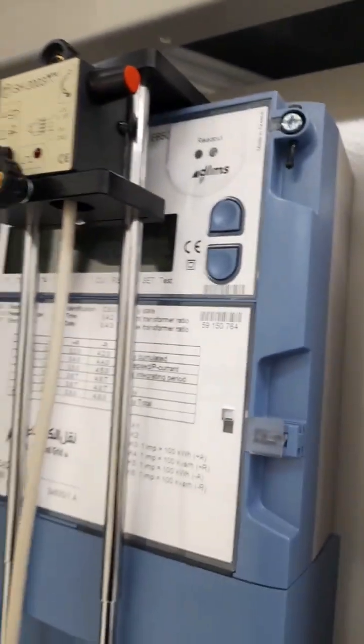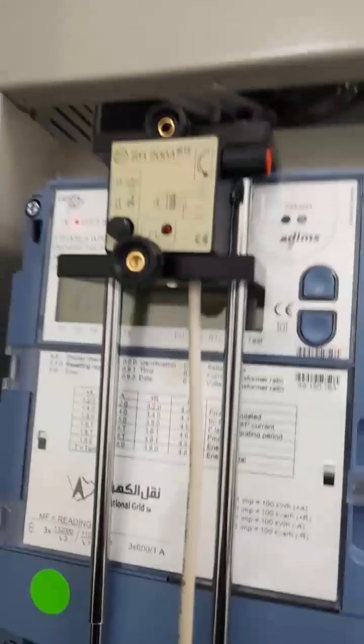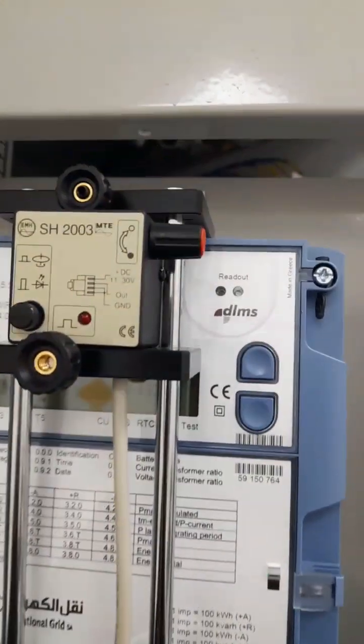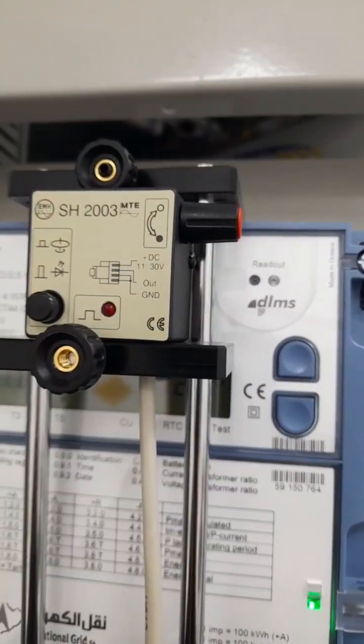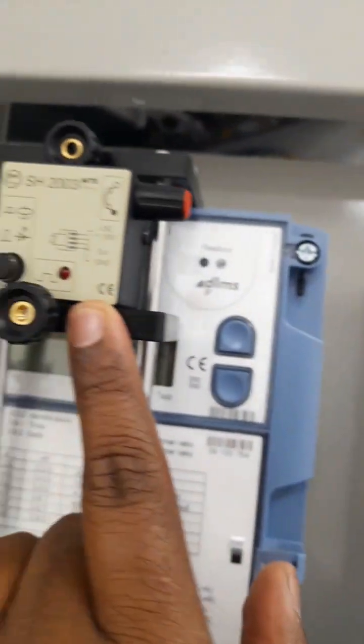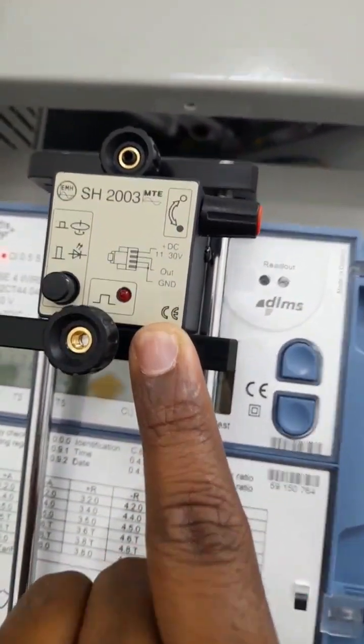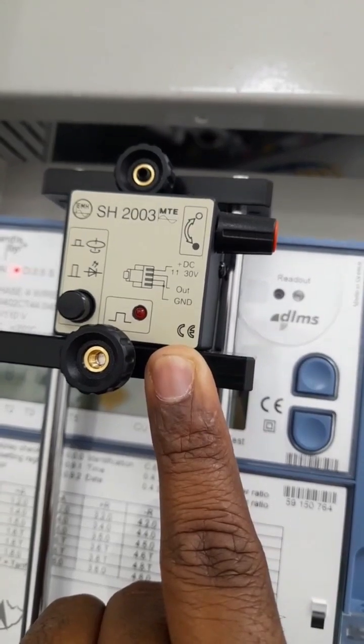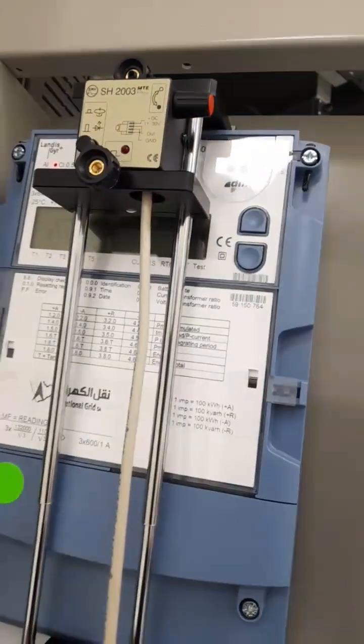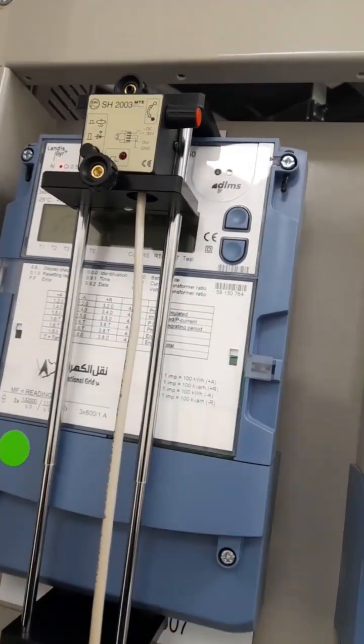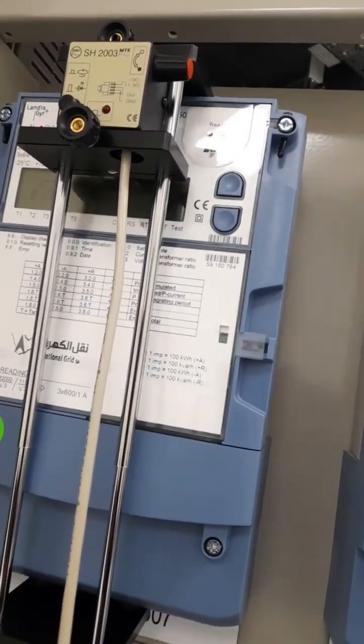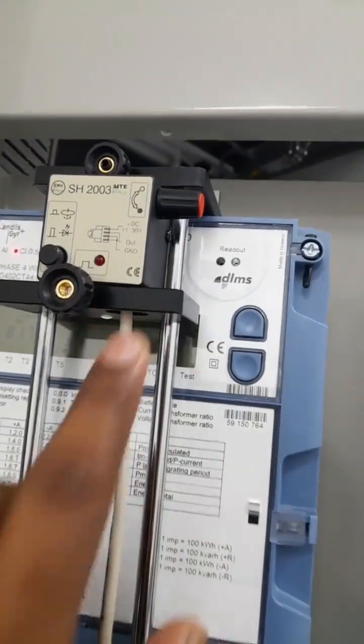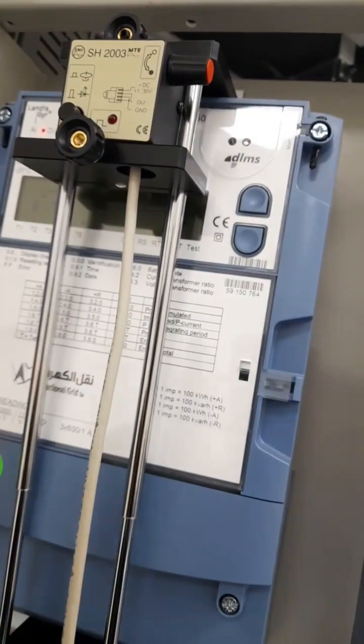Once you connect it, after you install, just try to inject some voltage and current. At that time, your LED must flash. This LED is over here. If it gives the flash, it means you installed this device properly. Your scanning head installation is fine. If you don't see any flash, you have to reinstall it again and try to match your LED with the actual meter LED.